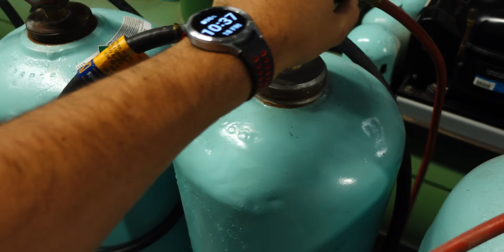I don't feel any standing liquid left in those, and another indicator is they're getting warm to the touch. We're running about 140 PSI on the vapor side coming into these tanks, while our chiller is sitting at about 46 or 47. So we've got a pretty good differential there.